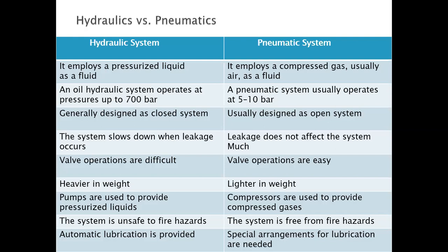a loss of power. Because if there is no leakage, then once the storage reservoir is filled, the sensor will stop the motor, will stop the compressor. But if there is any leakage, then the storage reservoir is never completely filled. Every time air is leaking from that point, so there is no cut in the power, right? So the compressor has to work continuously. So you can say power consumption is more, but from the efficiency point of view and work done point of view, there is almost no effect.